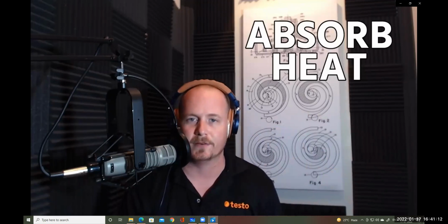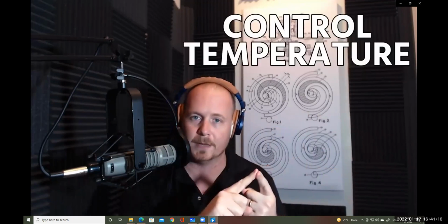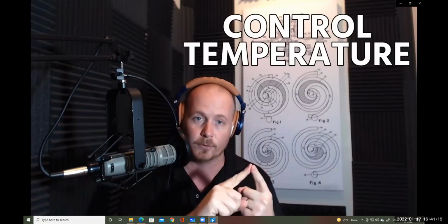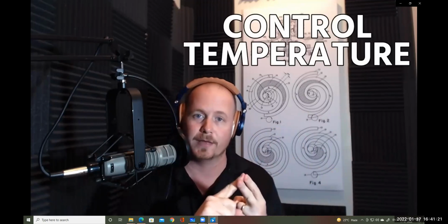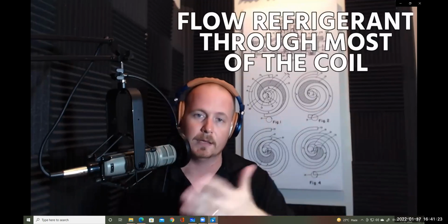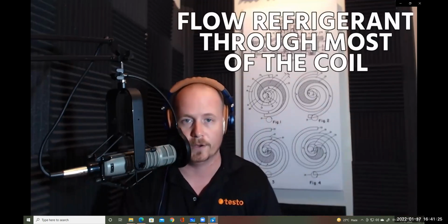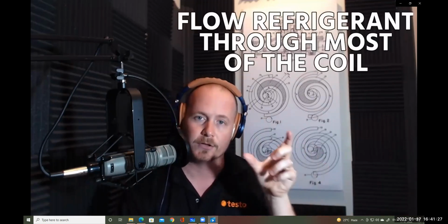So what we're doing with an evaporator coil, what we really care about, is making sure that we control the temperature to the temperature that we want that evaporator coil to be, and we also have to ensure that we flow refrigerant, that boiling liquid refrigerant, through most of the coil. Now, the last part of the coil is what we call the superheating phase.